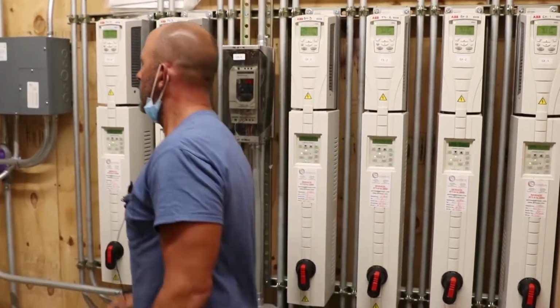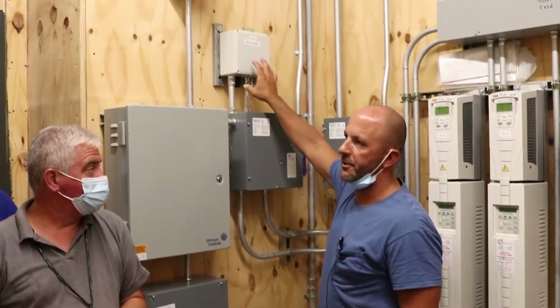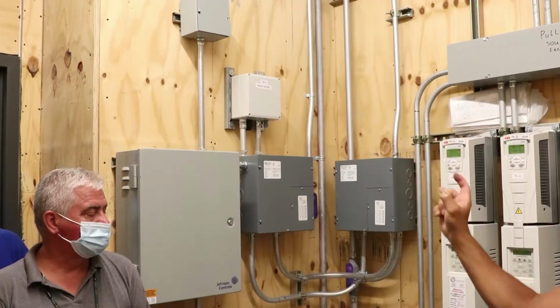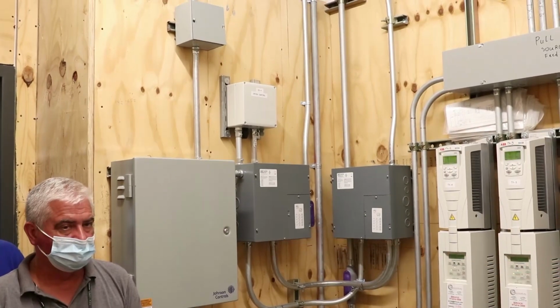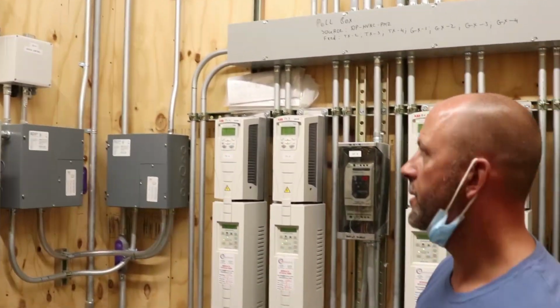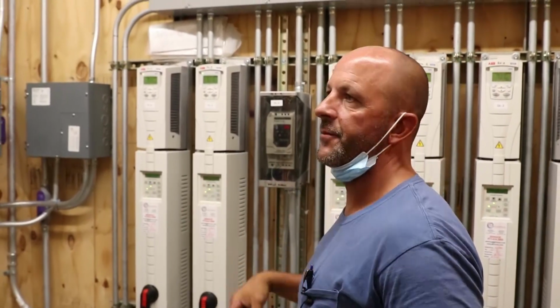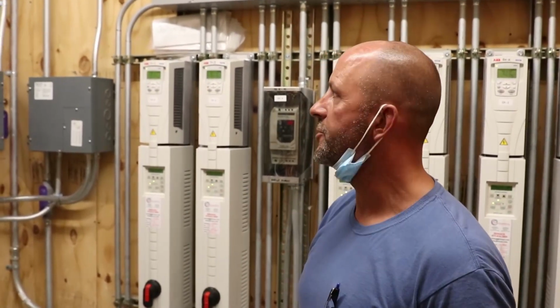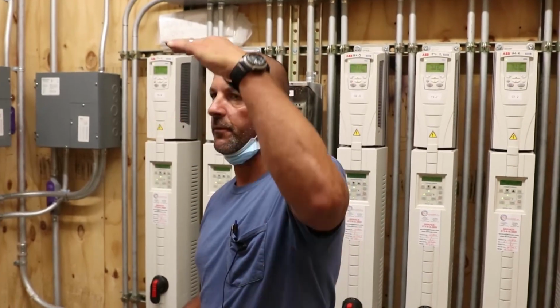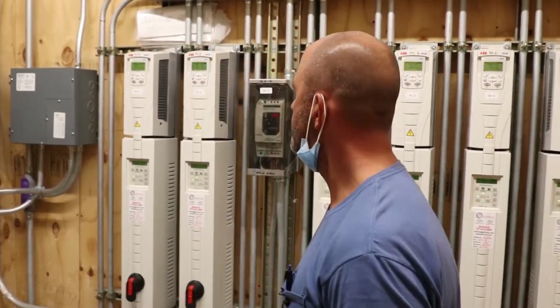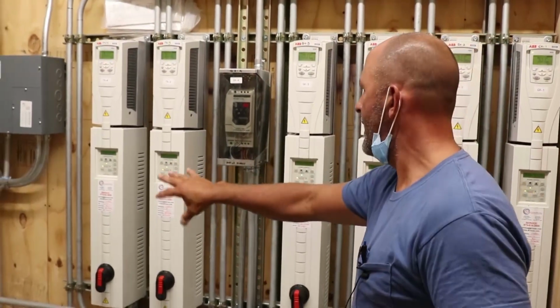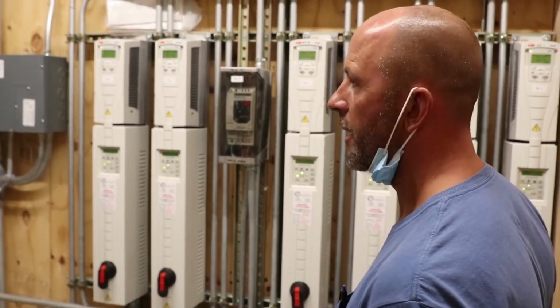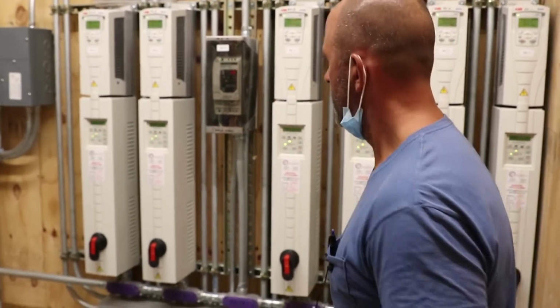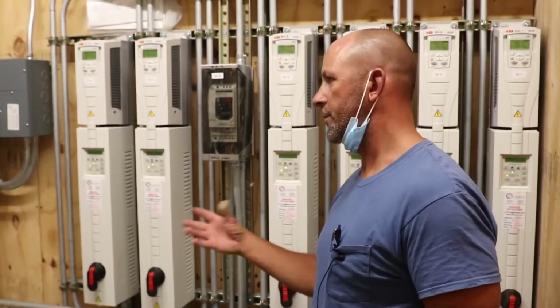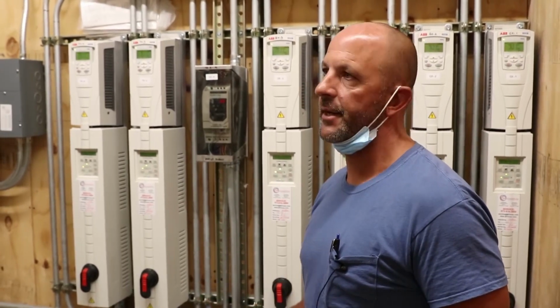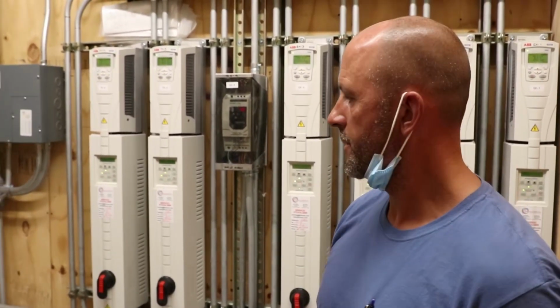Now this drive correlates with this controller. So basically what happens, they send power to this controller. They send a 3-wire out to a transmitter that's in the duct. It sees a drop in pressure. The transmitter says I need more and sends a signal to the drive, which ramps up and down based on a set point that the dryer guy sets based on his calculation of the floor heights. So that's why this is different. Other than that, all your drives are ABB drives, and they're all tagged. So I think we should just go to the other side, we'll look at those, and then I'll show you where the ones are downstairs, and then at least you know where everything is.